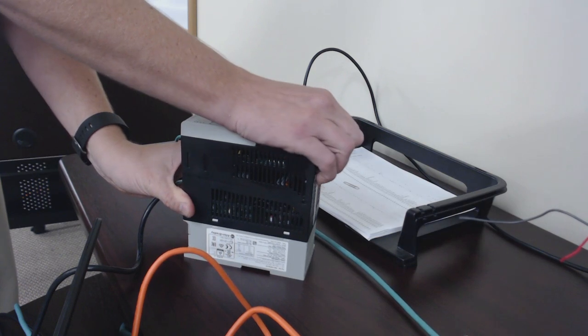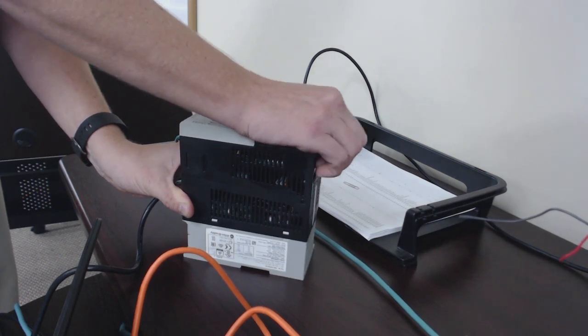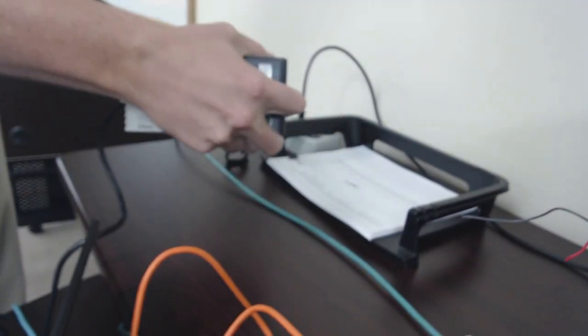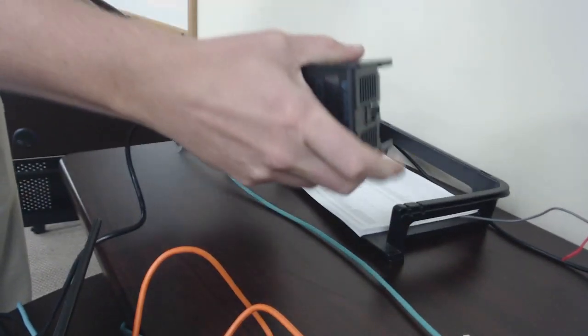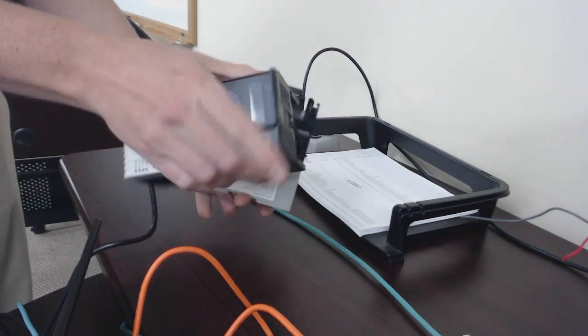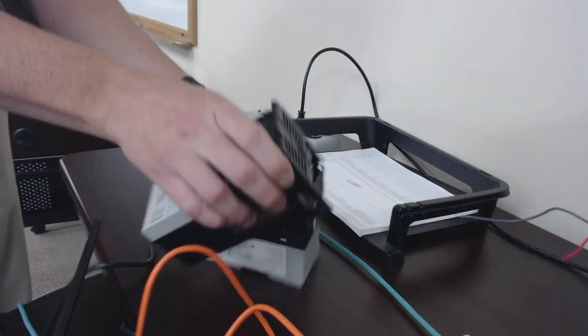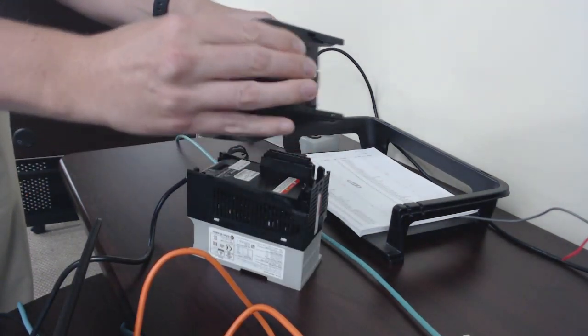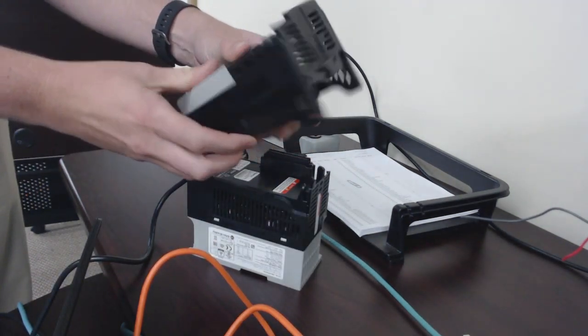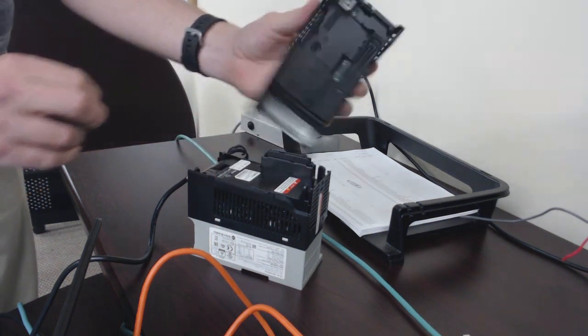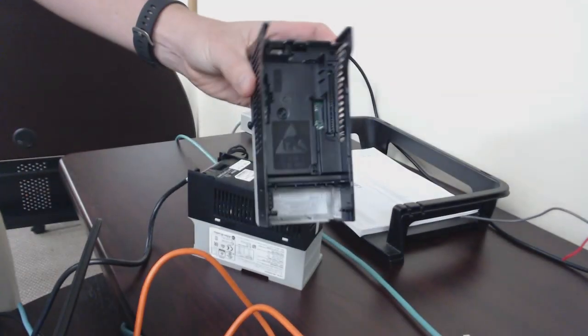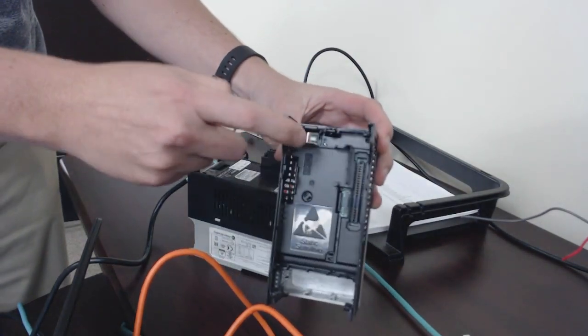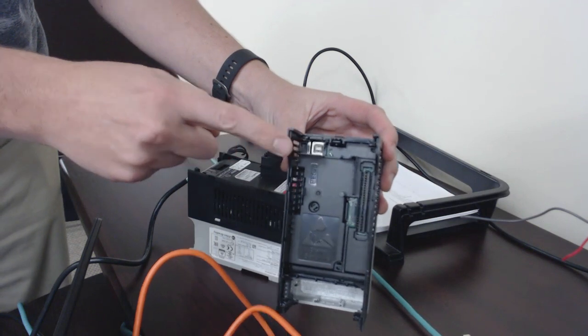If you have a power module go bad then you can leave the control module in place. All your parameters get saved in your control module so you can just replace the power module. You'll see how they separate like that using this locking tab on top. You have to slide it up and you can take this off. On the front or the back of here there is a USB port.